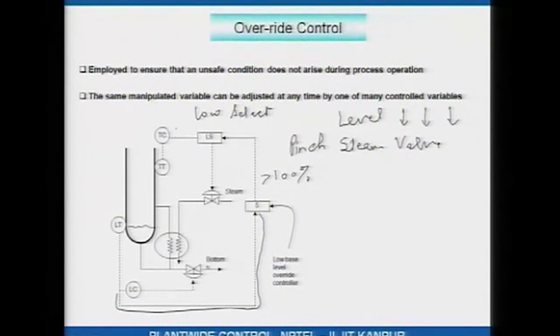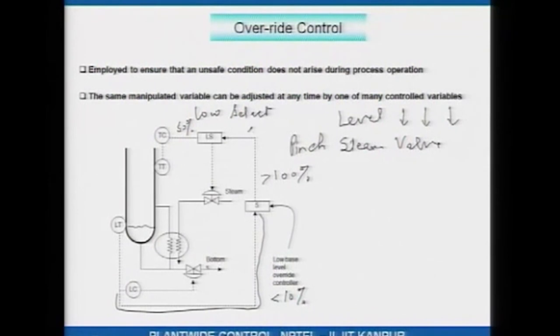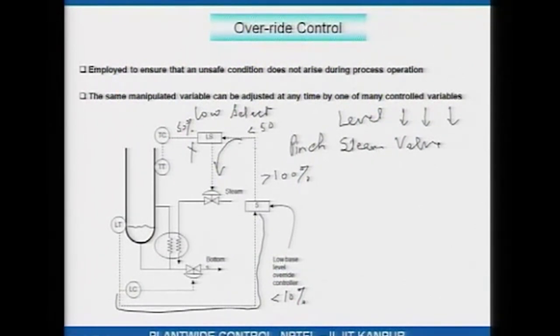If the level continues to go down, this signal ultimately becomes less than the temperature controller output signal, and the low select will now start sending this level-derived signal to the steam valve. For example, if the temperature controller output is 50 percent and the level goes below 10 percent, this signal goes below 50 percent, and then the low select will pass the level signal instead. This is an example of an override controller where the overriding circumstance is reducing level in the bottom sump of the column.